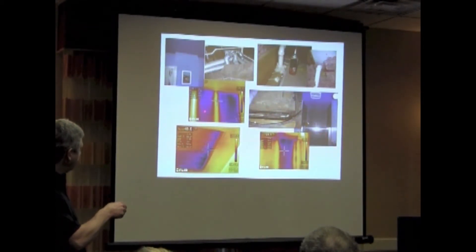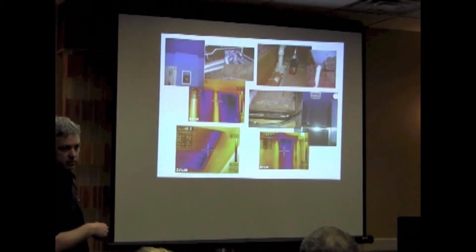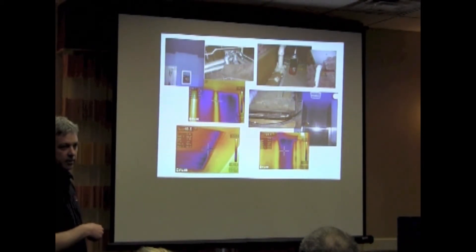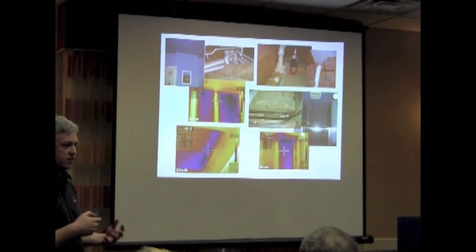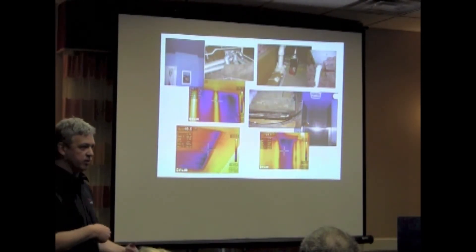Over here, the thermal camera is telling me that's just a cold surface — or a very wet surface, because if it's wet it would also show up as cold at night. That's the limitation of the thermal camera.